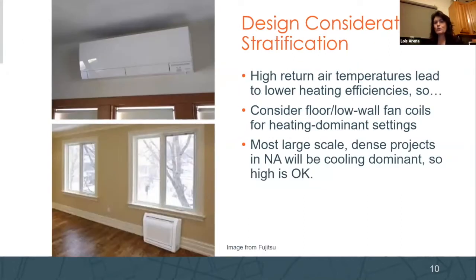Stratification of temperatures. If you're using a wall-mounted unit with a VRF system that's up high, you're going to have stratification, right? The temperatures are warmer at the ceiling than at the floor. So higher return temperatures lead to lower efficiencies. Also, if you're in a heating dominant setting, say you have a historic building that's more heating dominated, or you have a single family home that's more heating dominated and you're using a wall mounted unit in a mini split system, you want to maybe go lower, use a floor mounted system, which will increase the efficiency.